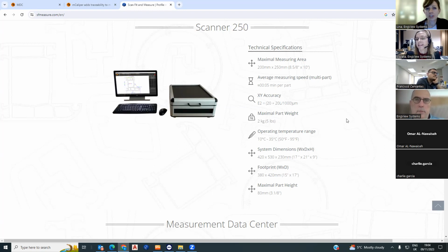We can send you a calibration glass. This scanner needs a calibration glass to send to you, and we can do the procedure remotely, by TeamViewer or Teams. We will do everything. What you should do is only place the calibration glass on the scanner and leave everything in our hands remotely. Then we will issue a special certificate, because our calibration glasses are produced in Germany. We have DAkkS certificates for them.